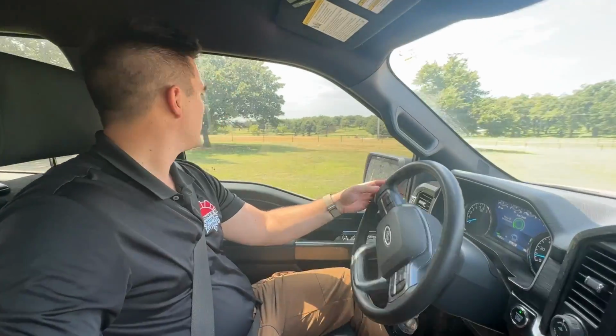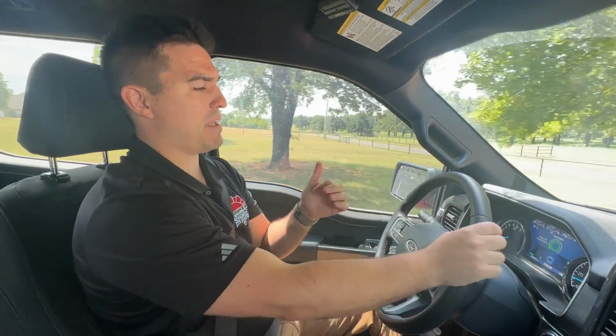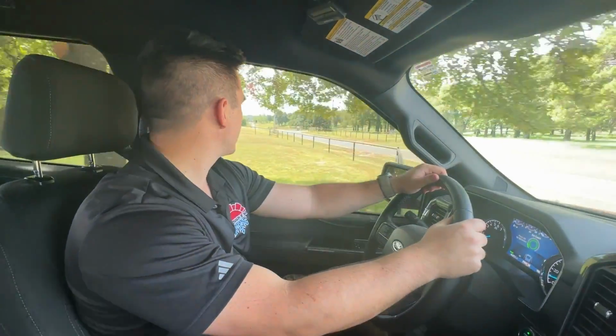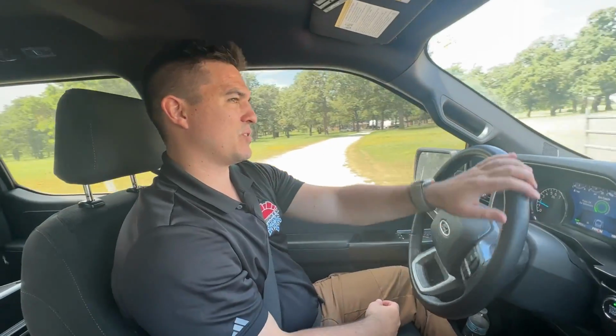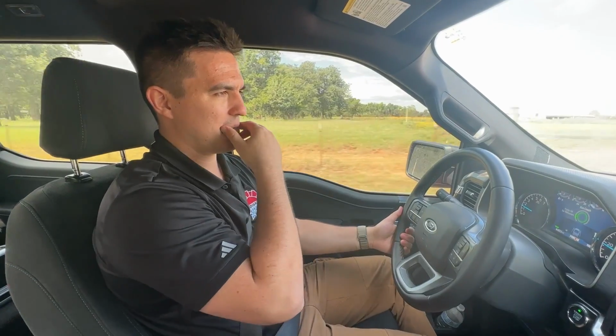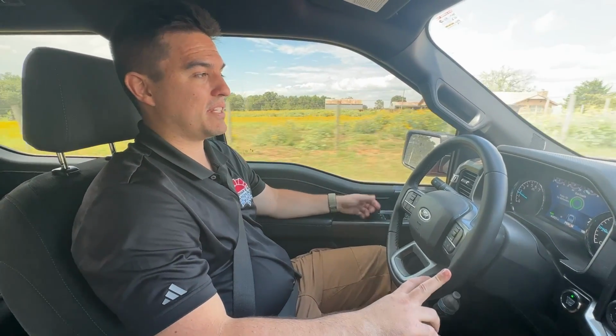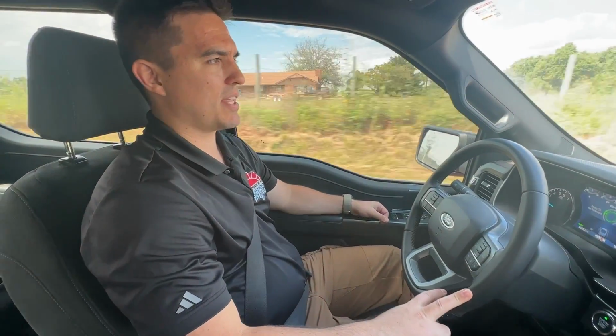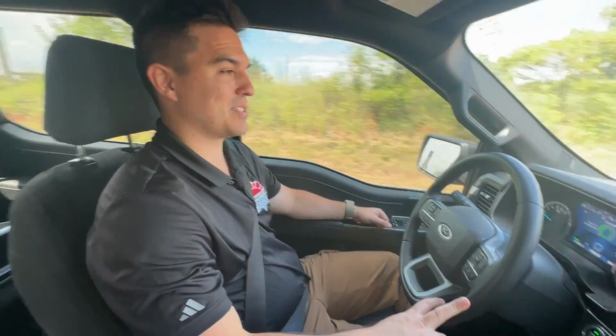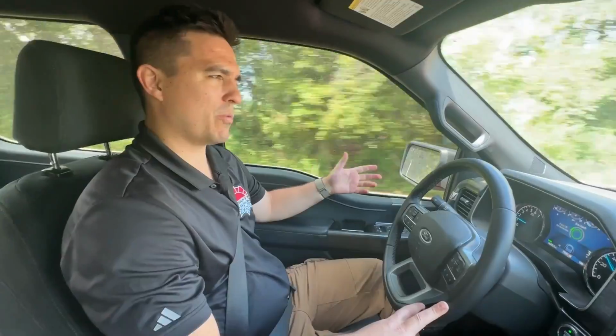Just finished up. Everything went well. It was good. Recap, they have a 2.5-ton system, and it may be oversized for their comfort preferences. They set the thermostat around 77, and the square footage of the master bedroom, grandma's room, and the bathrooms associated are less than 800 square feet. And so at that point, with them putting the thermostat at 77 degrees, their 2.5-ton system, I would say, is oversized. Maybe one of the reasons why the system is failing around 10 years, a little bit earlier than what you would want the system to fail or have major system breakdowns.